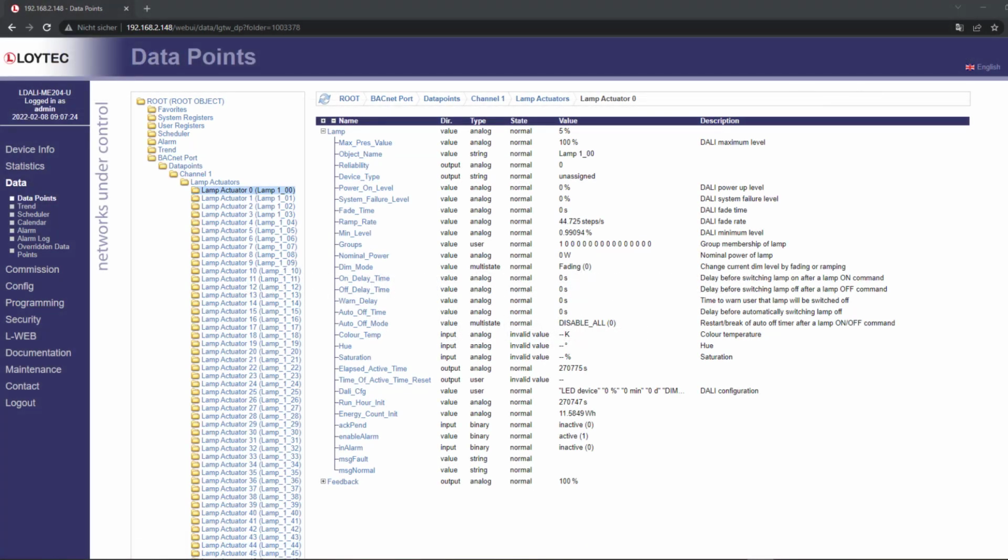Feedback values of a lamp actuator can be different from the writing data point, depending on where the dim level has been written from. A DALI command can either be written directly from a constant light control application, a button model, a data point button, or directly from the DPAL layer, that is in this case of lamp actuator, the data point lamp itself.